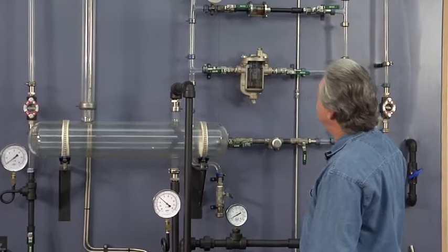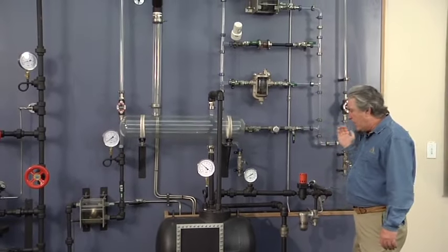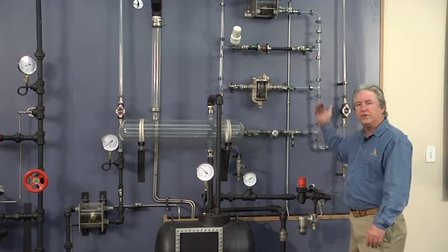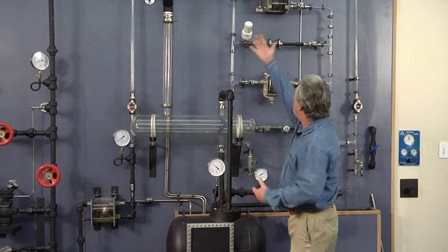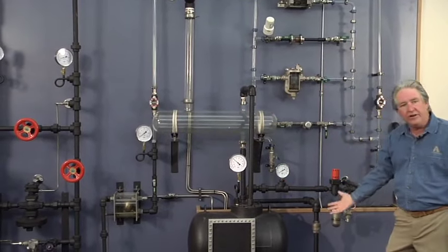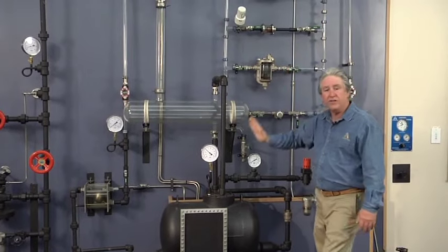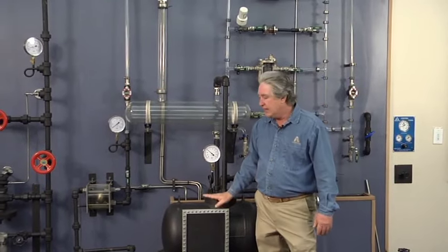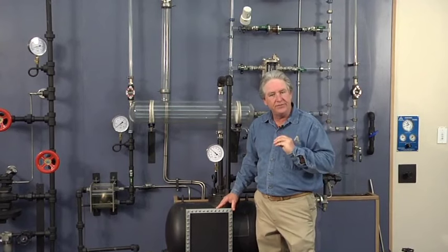The inlet pressure that's fed to a heat exchanger is normally always dependent on what the process flow is telling this control valve that it needs. However, what affects all of this equipment down here, whether it's steam traps or pumping traps, is the actual outlet pressure of the exchanger.